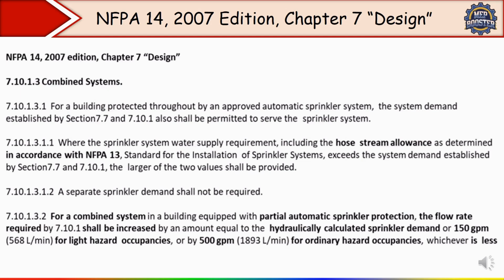Now here you can see in NFPA 14, 2007 edition, chapter 7, the design requirements are given for combined system. In this slide, every point written is taken from NFPA 14, 2007 edition, chapter 7. So the design specifically discusses the combined system. Try to understand the combined system as I told you in the starting. All of you know that a combined system is a fire protection system where the automatic sprinkler system and standpipe system share the same water supply.